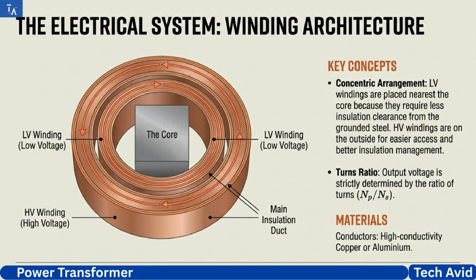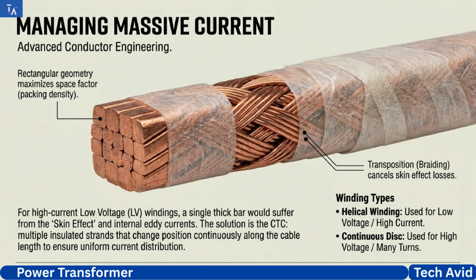But handling massive current brings its own nightmare, the skin effect. At high currents, electricity tries to flow only on the surface of a conductor, wasting the interior. The solution for giant low-voltage windings is brilliant engineering, the continuously transposed cable. It's a bundle of many insulated strands that constantly change positions along the cable's length, forcing the current to distribute evenly across the entire cross-section.